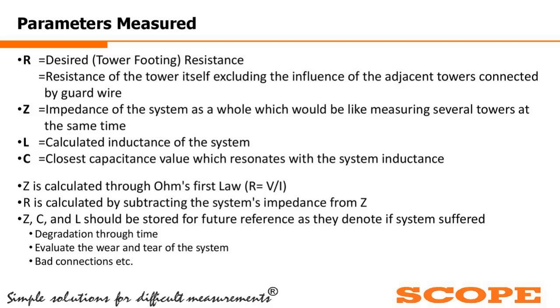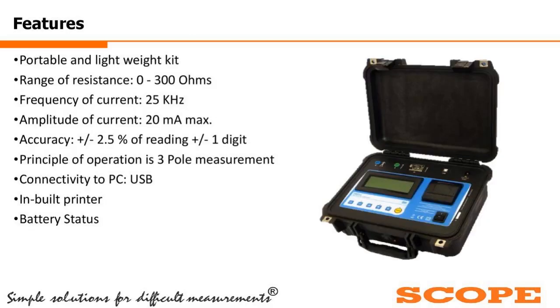So my major concentration is R, but I will not be neglecting or discarding the data, whatever is given, Z, C and L, by the instrument, because those have to be kept as a reference for future. So if the system changes, then I will be able to correlate if degradation has happened, if loose connections are developing, how the wear and tear has happened, whether the earthing system itself is going faulty or something like that. All the parameters I can get.